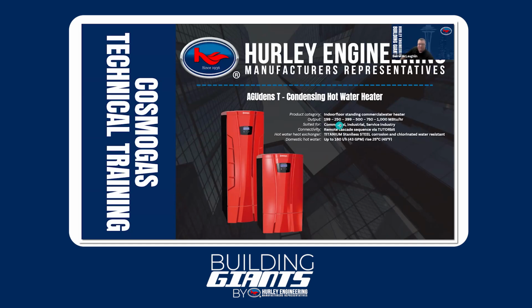So the 250,000 BTU heat exchanger would have 15 wraps of the water tube inside the heat exchanger, while the 199 and 399 would only have 13 wraps. There's actually less surface area for the BTUs. So, and then you can see some of the other items here. It's up to 43 gallons per minute total max of hot water output at a 45-degree Fahrenheit rise. So that can vary quite a bit. But with a million BTUs, 20 to 40 gallons per minute is very acceptable depending on your delta T.